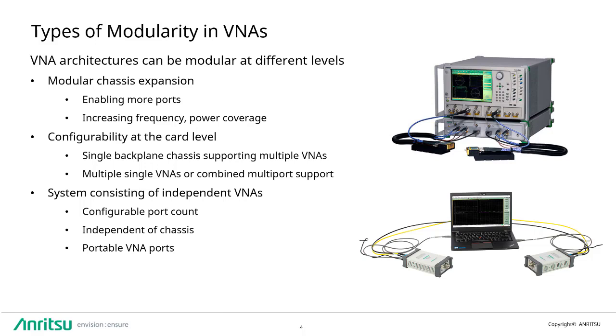Modular architectures can be classified into three major classes. Modular by chassis, where test sets and other instrument building blocks are added to a base VNA to add functionality like additional ports or increased frequency or output power. This type of modular VNA must have expansion support built into the base VNA architecture, which differentiates it from the typical non-modular integrated VNA.